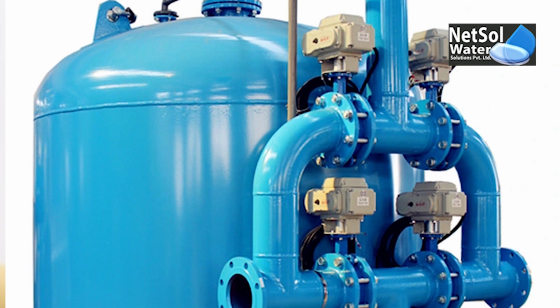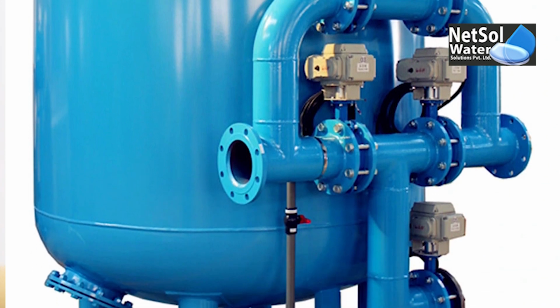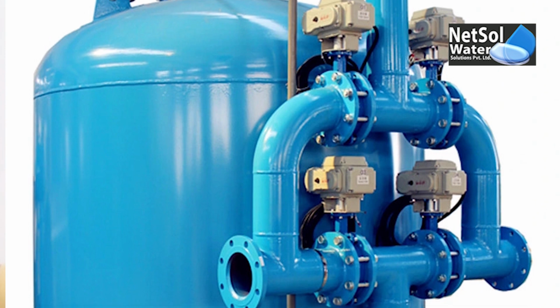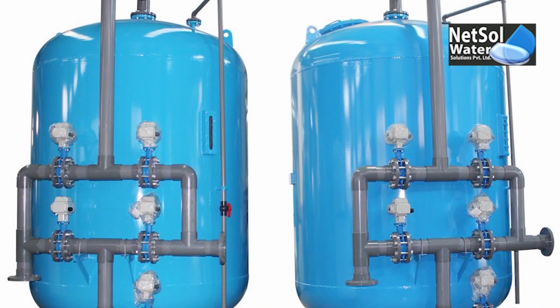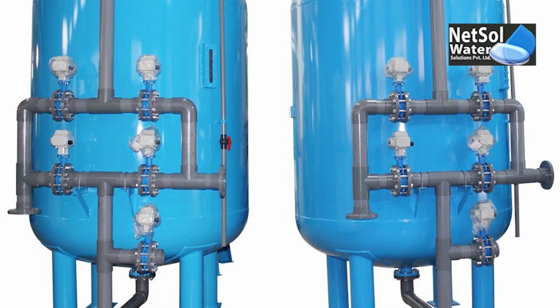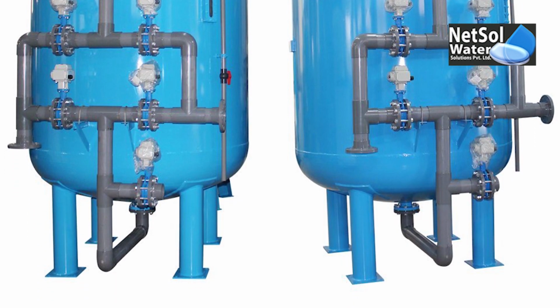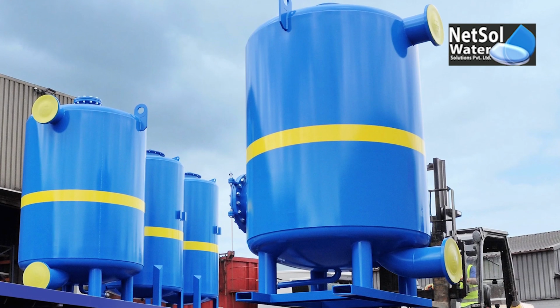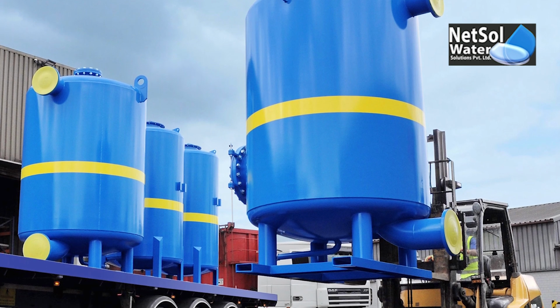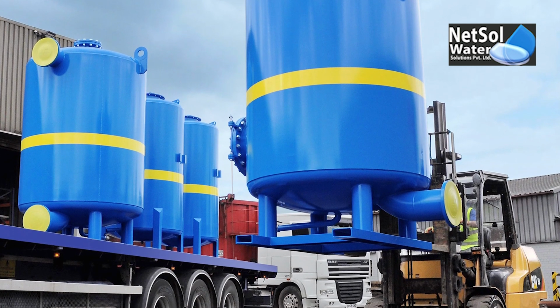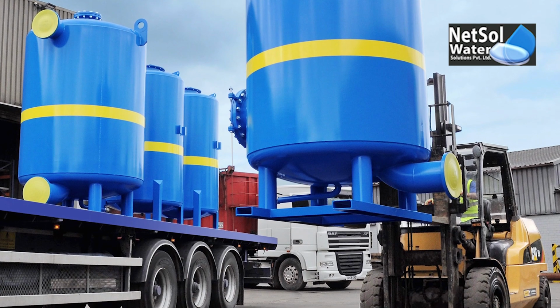For example, if it is working for chlorine removal, then activated carbon may be used to remove chlorine with little degradation or damage to the carbon. Dechlorination occurs rapidly and flow rates are typically high. However, this process requires an extensive amount of surface area, and organics in the water will eventually fill up and block the pores of the carbon. Ultimately, the activated carbon filter will need to be replaced as its ability to dechlorinate water will slowly decline.